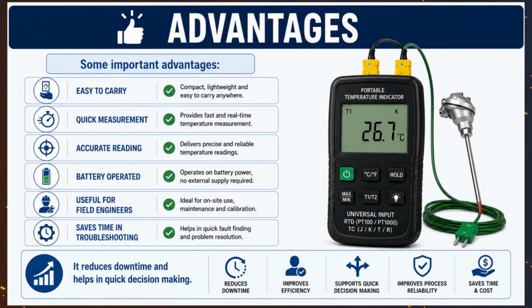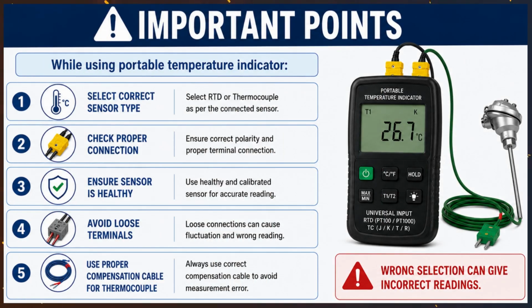Advantages. Some important advantages: easy to carry, quick measurement, accurate reading, battery operated, useful for field engineers, saves time in troubleshooting, it reduces downtime and helps in quick decision making. Important points. While using portable temperature indicator, select correct sensor type. Check proper connection. Ensure sensor is healthy. Avoid loose terminals. Use proper compensation cable for thermocouple. Wrong selection can give incorrect reading.